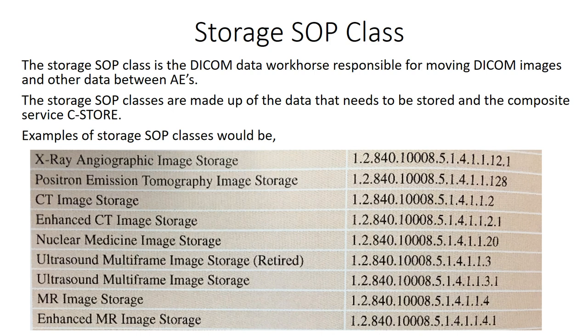Storage SOP class. The storage SOP class is the DICOM data workhorse, responsible for moving DICOM images and other data between AEs. Think about what a PACS system's primary function is. Its primary function is to store images. CT images, ultrasound images, nuke med images, MRI images, every kind of image taken gets stored in the PACS system. That's why the storage SOP class is the data workhorse. The storage SOP classes are made up of the data that needs to be stored and the composite service C-STORE.